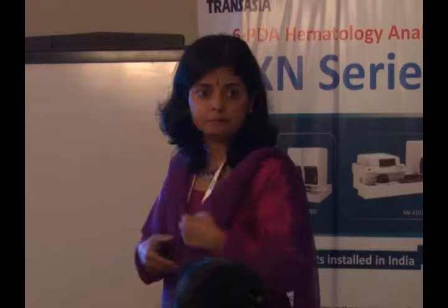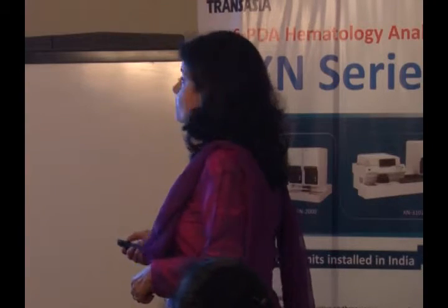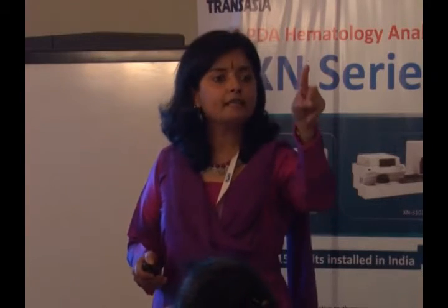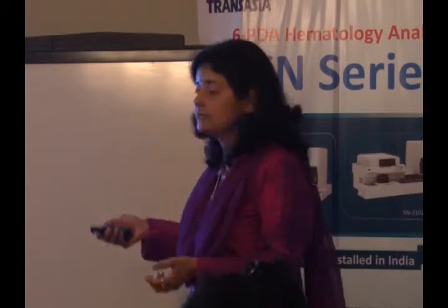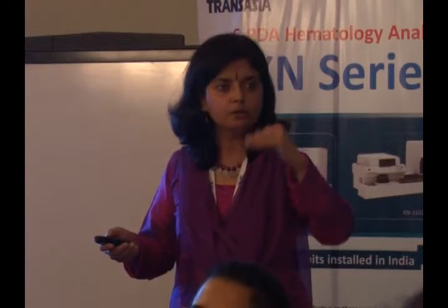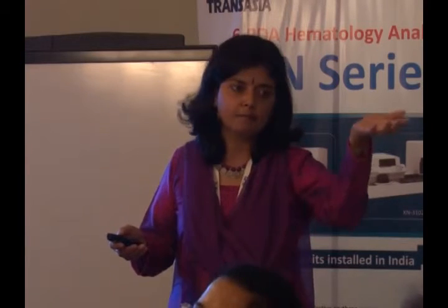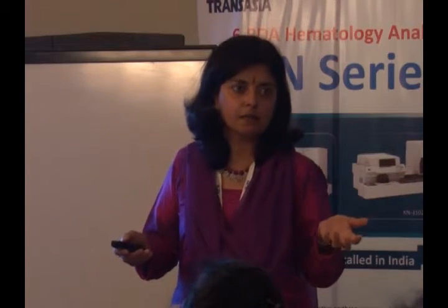Ma'am, can you elaborate on that MDS parameter? Yeah. It used to be called NEUT-X, NEUT-Y in the earlier machine. In the XE, NEUT-X, NEUT-Y, now NEUT-SSC, side scatter. It just shows you that they are hypogranular neutrophils. Maybe Pelger-Huet, maybe any hypogranularity.